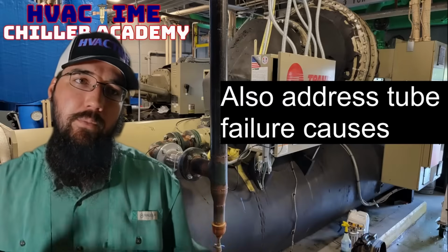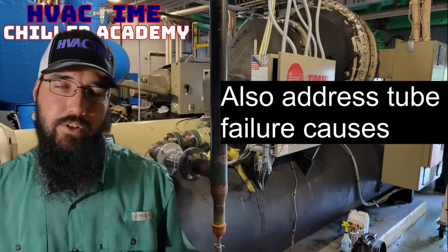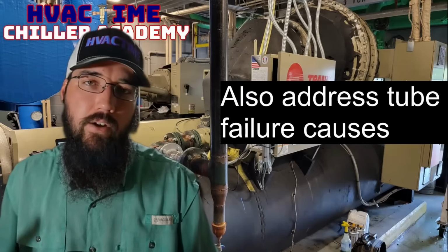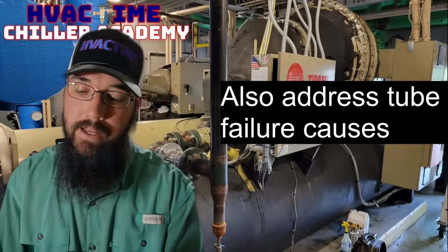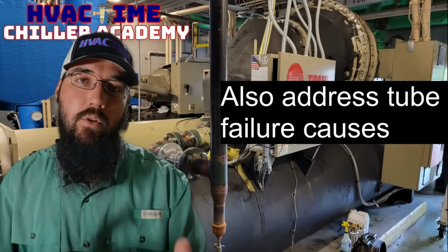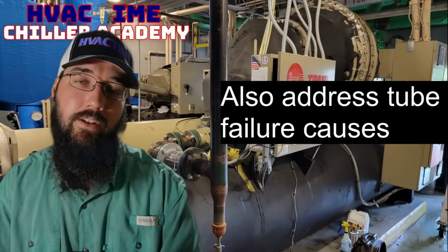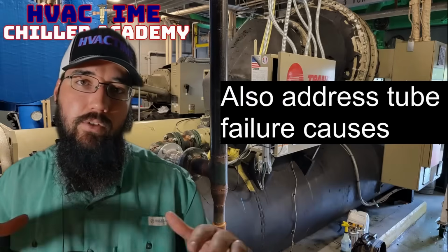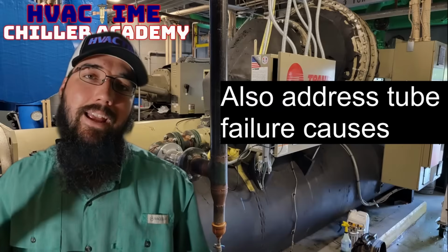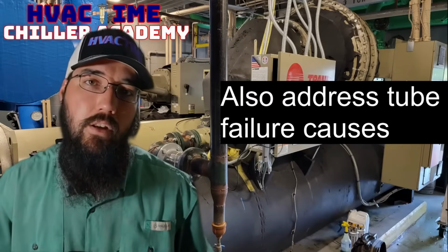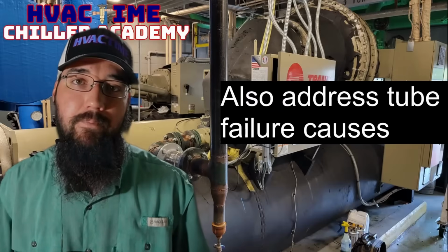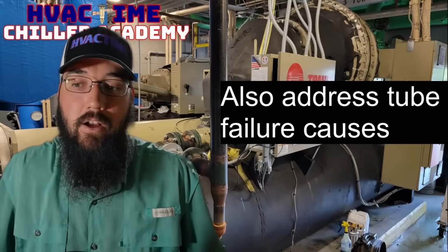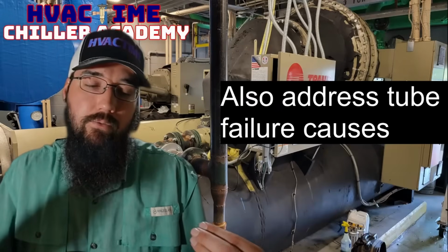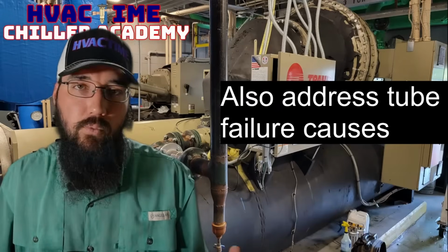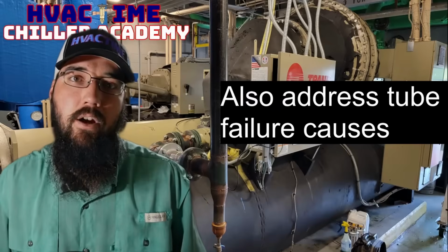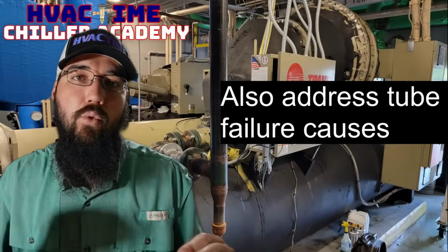Now, aside from just a freeze condition, if you're not careful or don't follow proper practices with recovery and charging, you will also create that same freezing condition, because essentially any tubes that are submerged below the liquid refrigerant, and that liquid refrigerant is allowed to get below freezing temperatures in saturation, which typically it's a common thing to have happen when you're recovering.